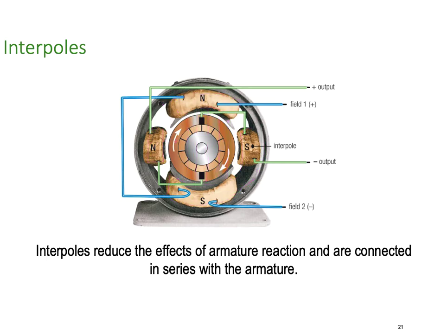I'll just clear that. So if this is our new pole arrangement, which operates across here, just quickly draw them in for you, we're now going to get a magnetic field that looks far more like this. And we're going to pretty well eliminate armature reaction because we've got magnetic field all the way across the machine, not just vertically through the machine.